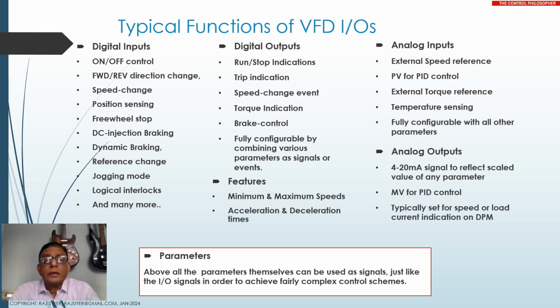Likewise for digital outputs, we have run stop indication, trip indication. There's a speed change event. There's a torque indication. Now this is important for cranes and things like that, because in cranes this digital output is used to release a brake. The brake must not be released till the VFD has developed enough torque. Otherwise there will be an impulse loading on the hook of the crane. But this kind of crane and winch application is a separate profession in itself. But just be aware that these features exist within drives.